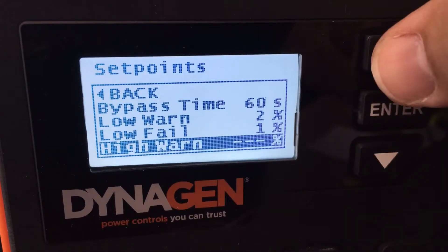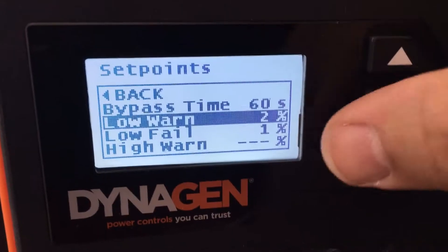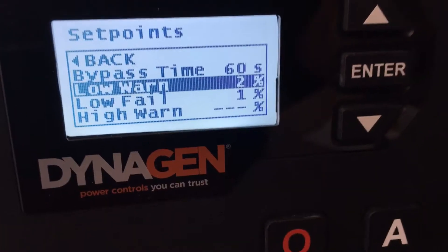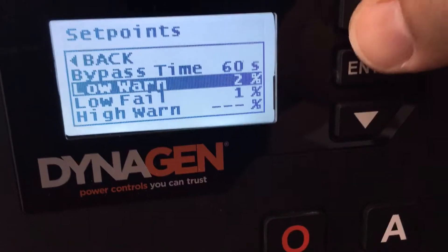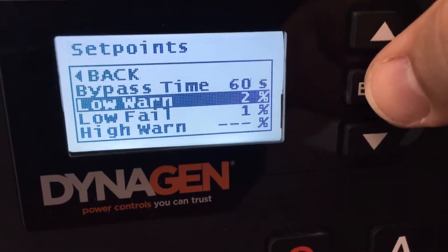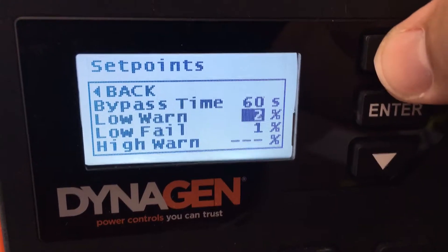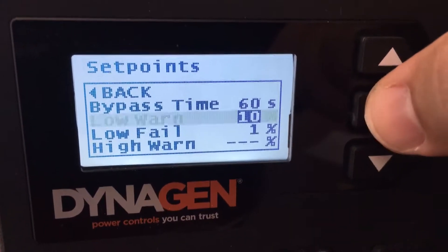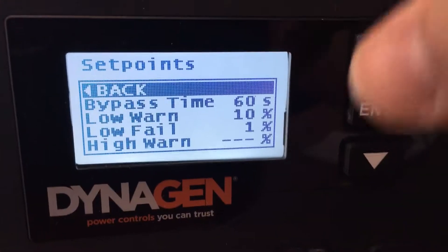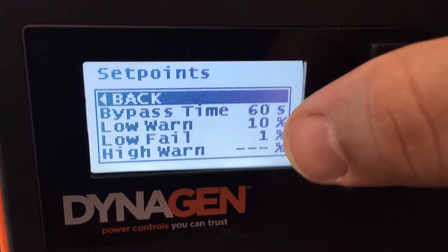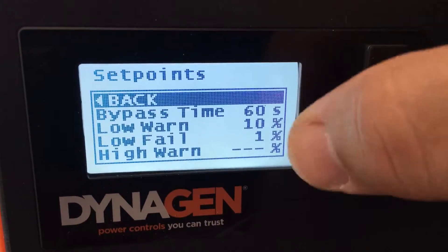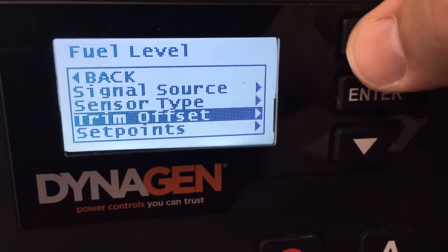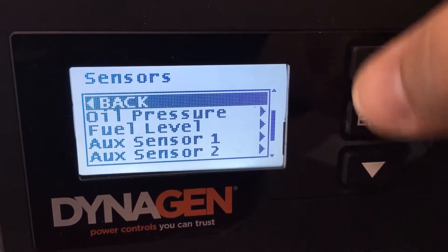Also play with the high level warning. You may find it's anywhere from 90 to 100%. I believe it's every 10 centimeters that is a change in value on the sensor, so adjust it accordingly. Your low level, maybe you'll start at 10%. If you set it to fail, then the engine will actually shut off when it reaches that level. We don't want that to happen when you're using your generator in your application. To get out of this, we just back out.